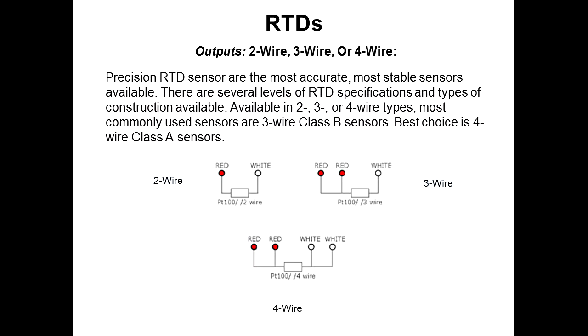So what we're doing is we're running a current through here and it goes through the sensor and goes out, and this goes back to your meter. The current also goes down this leg and this leg to the meter, and connected between these two is an ohm meter. I don't care anything about this. All I care about is the difference from here to here. So this ohm meter is reading these two, and that's giving me my temperature reading. And this is your power circuit. On the 3-wire, we're assuming this missing wire will be the same as this, and that's not always true. Not a lot of difference, but there might be a small error depending on the accuracy you're requiring.